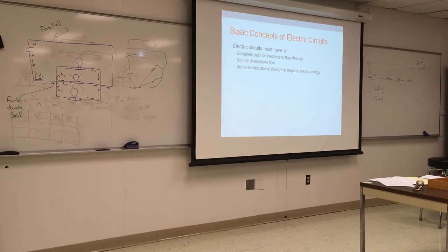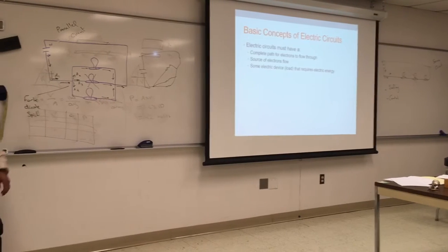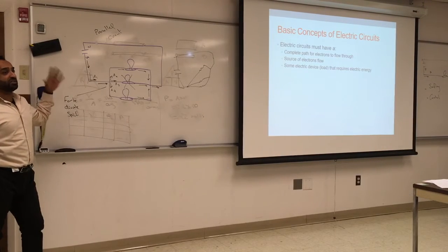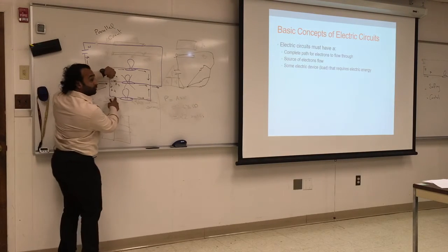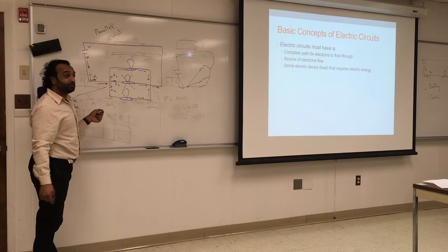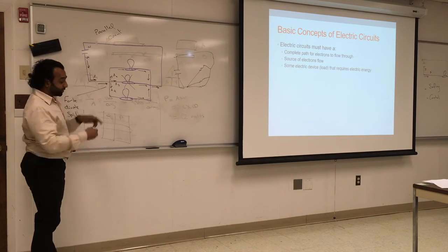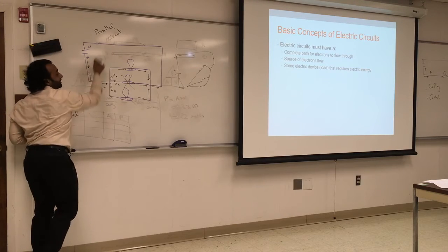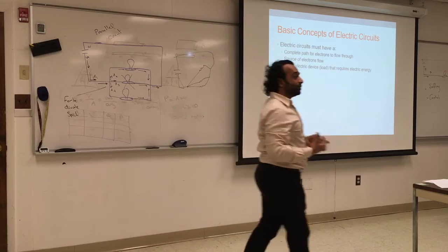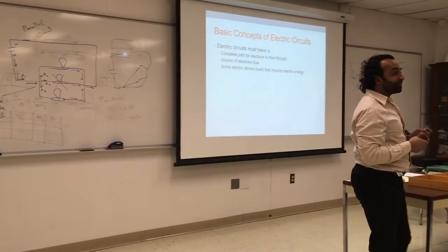We had this today in the lab. Somebody was trying to wire an aquastat. They wired everything. One of the wire nuts for the neutral was loose. Nothing worked. You go check for power here, you'll find power. But you have to keep tracing the power until you find where it is broken. So you have to achieve the complete circuit. You need a complete circuit. And I'm going to keep saying that because this is one of the biggest issues.